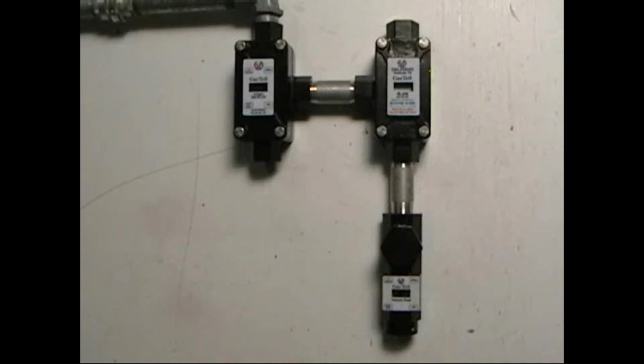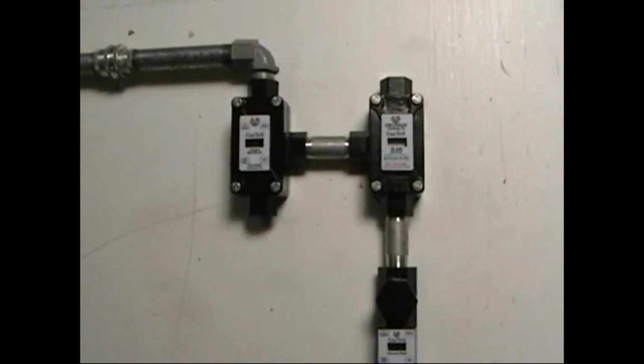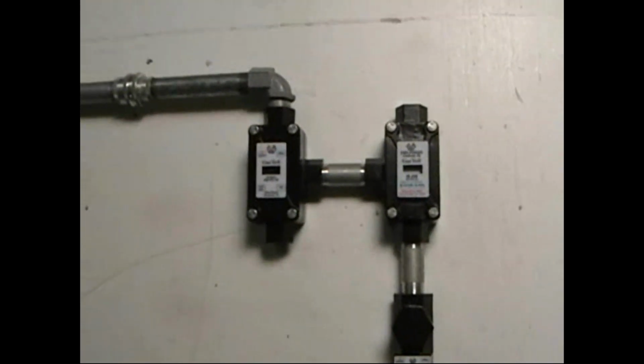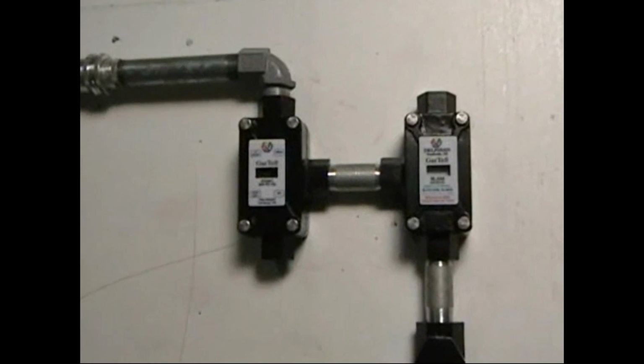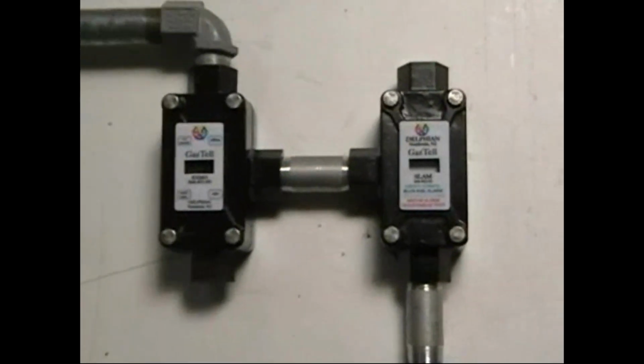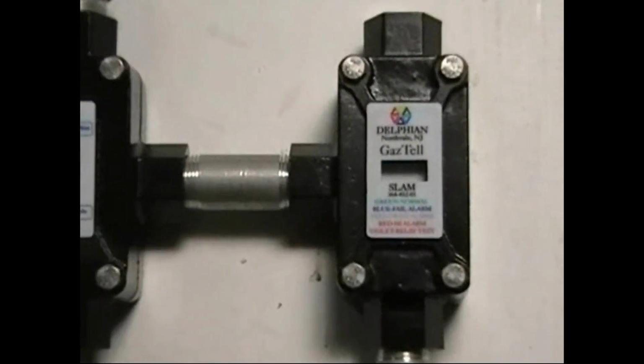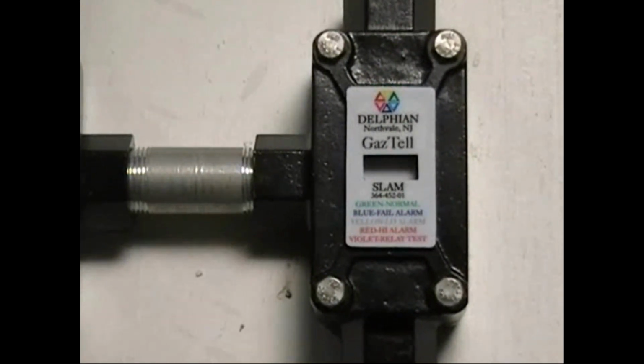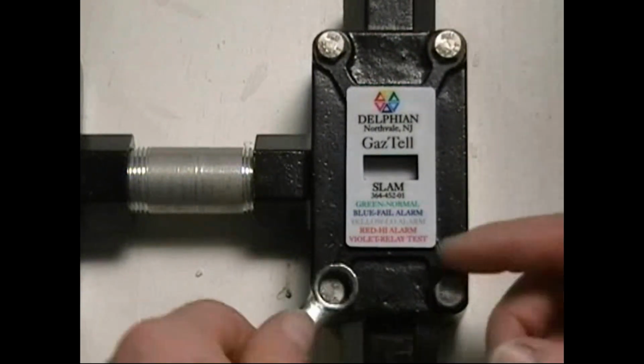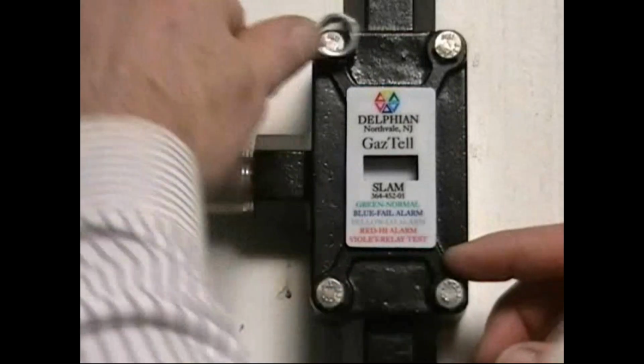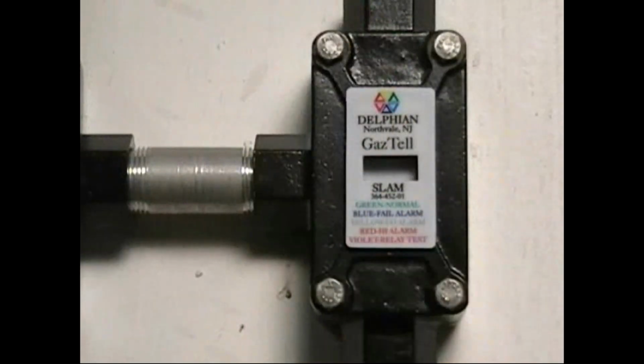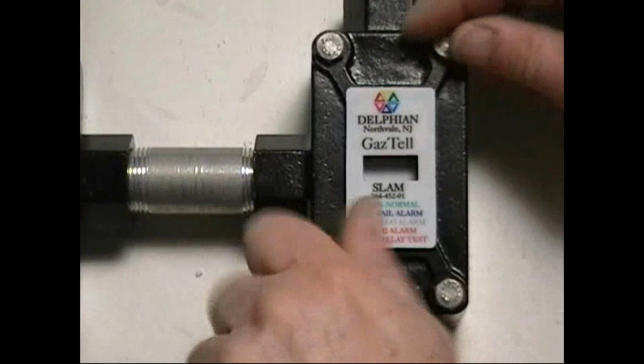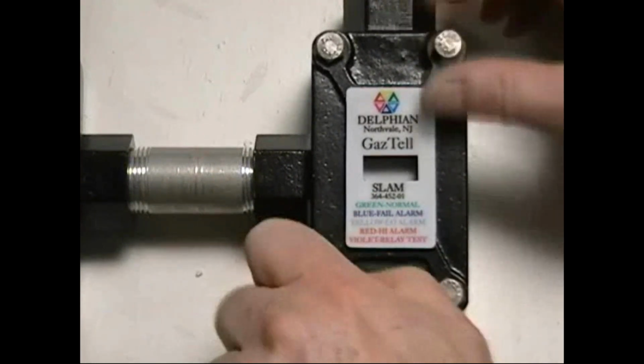Shown here are the detector head, the simple local alarm module, also known as the SLAM, which is a relay module for low, high, and fault relay contact loads, and the extension module, also known as the XMO, which is typically used when the detector is installed in locations that are inaccessible for viewing, or to make it easier to perform calibration, such as up links, or if they are mounted down into pits. These modules can be mounted up to 400 feet between each other and the detector head.